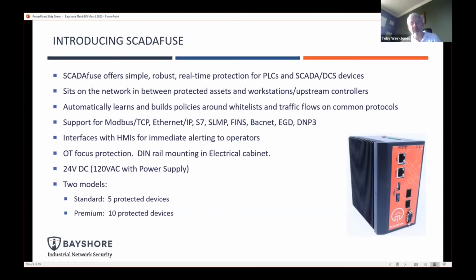The two basic models for the endpoint SCADA fuse: the standard device will protect up to 5 assets, and the premium device will protect up to 10. Same hardware, this is just a licensing distinction. The idea is that these are not expensive to purchase, they're easy to install, and most importantly, they learn on their own. So when you first deploy these devices, they build an automatic profile of all the rules necessary to reflect normal and safe activity. And it organizes it by protocol and by source and destination IP address, and then by function code for all the protocol activity. And I'm going to show you a little bit about how that works in a minute.